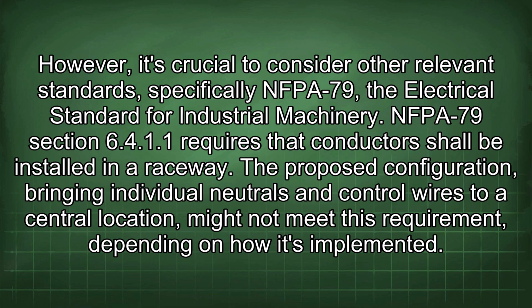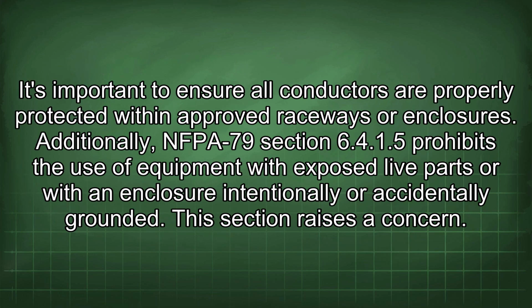NFPA 79 Section 6.4.1.1 requires that conductors shall be installed in a raceway. The proposed configuration, bringing individual neutrals and control wires to a central location, might not meet this requirement, depending on how it's implemented. It's important to ensure all conductors are properly protected within approved raceways or enclosures.